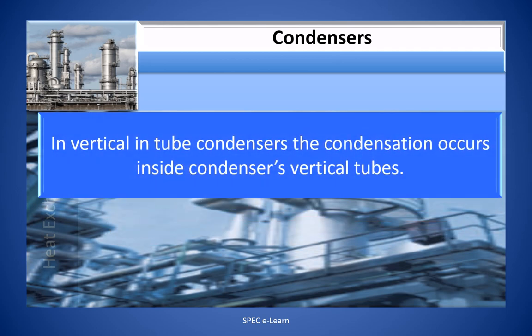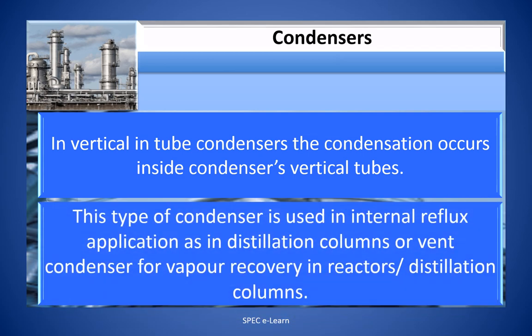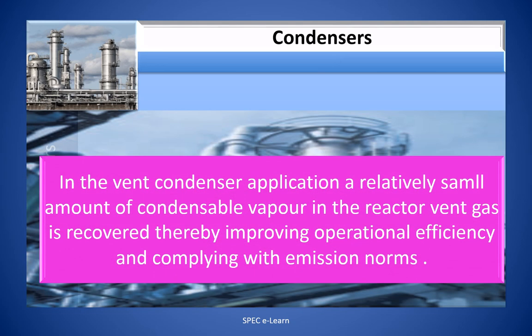In vertical in-tube condensers, the condensation occurs inside the condenser's vertical tubes. This type is used in internal reflux applications such as distillation columns, or as a vent condenser for vapor recovery in reactors or distillation columns. In the vent condenser application, a relatively small amount of condensable vapor in the reactor vent gas is recovered, thereby improving operational efficiency and complying with emission norms.